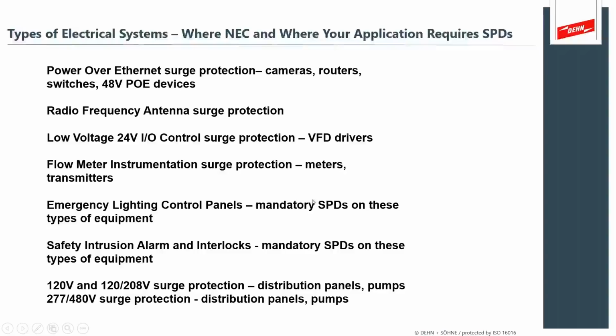Emergency lighting panels. This is an area where it's mandated to have SPDs. Safety intrusion alarms on that high voltage. For instance, your high voltage MCC cabinets will have access doors with little intrusion safety switches. Those safety interlocks have to have SPDs to meet the code requirements. OSHA and the NEC and NFPA code requirements, they look very carefully at that circuit. And then just standard 120/208, 277/480, I call it just standard distribution. These are the applications which are ubiquitous through the process control.